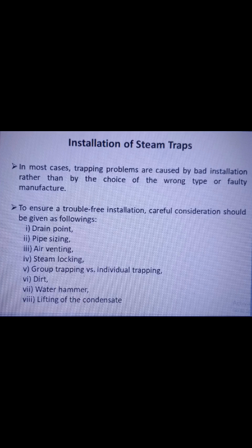It is often better not to lift the condensate directly from the trap, but to let it flow by gravity to a pump or a pumping trap, which can then do the lifting.